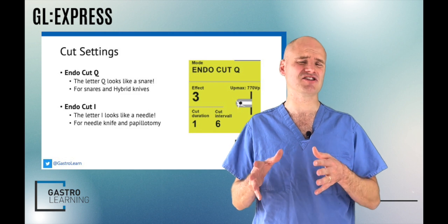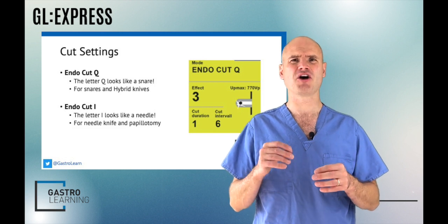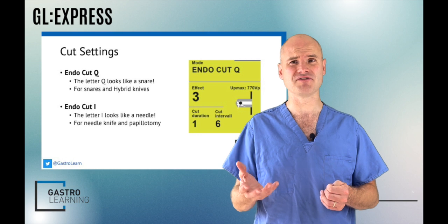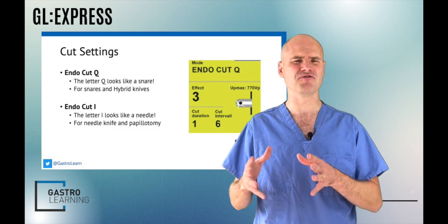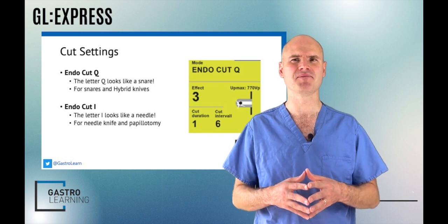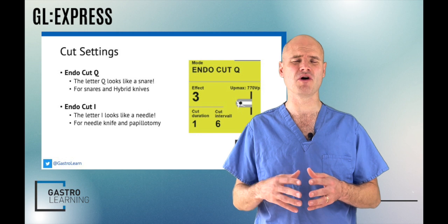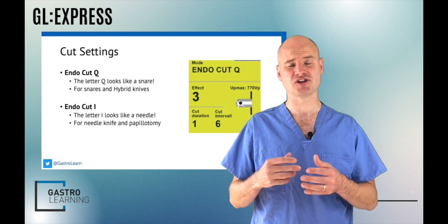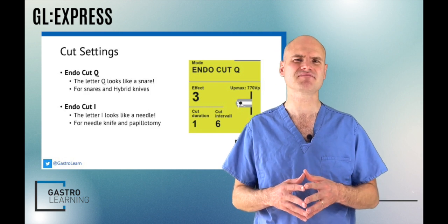The first thing you have to select is the mode, and this is selecting between Endocut Q and Endocut I. Endocut Q is designed for cutting over large surface areas, in other words when you have a snare. We also use it for some ESD work with hybrid knives. The letter Q looks like a snare so it's easy to remember. Endocut I is used for needle knife work and papillotomy. We can also use it for small needle-like ESD knives such as a dual J knife. The letter I looks like a needle so it's easy to remember.